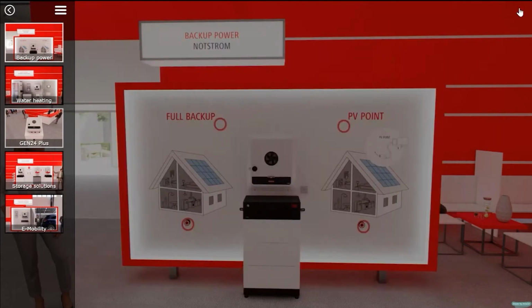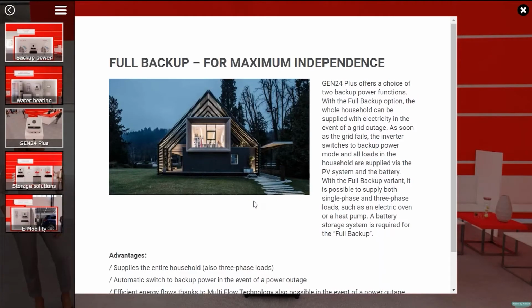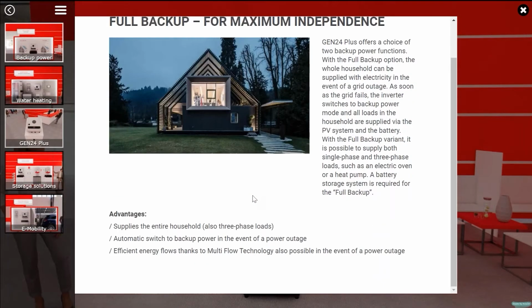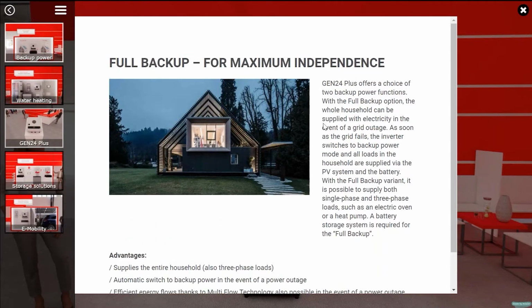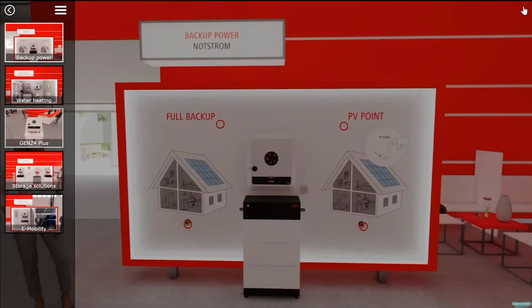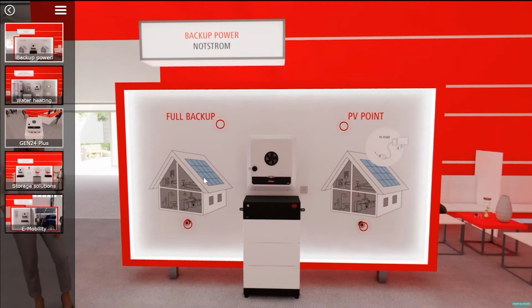If you want, you can do a full backup, but again for commercial it depends what size we're talking about. You can have your essential and non-essential loads separated, and you can have up to 9 kilowatts of backup depending on which battery and inverter you have - that's the maximum you can do. This is an automatic disconnect, so we have contactors installed in the main switchboard to do this job. Still applicable for your small commercial job if you want a backup solution.